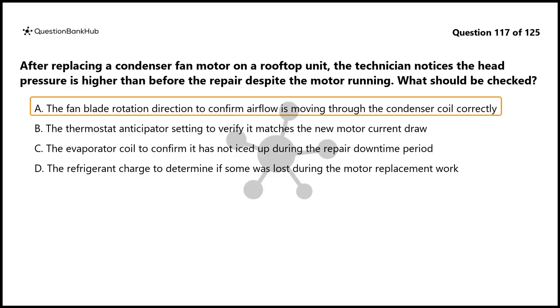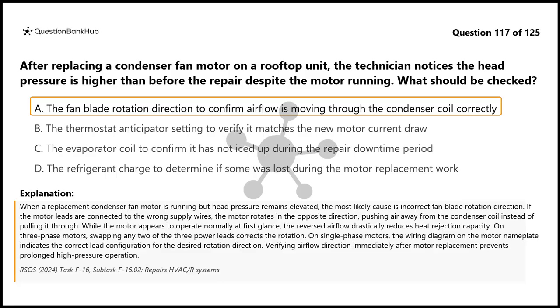The correct answer is A. When a replacement condenser fan motor is running but head pressure remains elevated, the most likely cause is incorrect fan blade rotation direction. If the motor leads are connected to the wrong supply wires, the motor rotates in the opposite direction, pushing air away from the condenser coil instead of pulling it through. While the motor appears to operate normally at first glance, the reversed airflow drastically reduces heat rejection capacity. On three-phase motors, swapping any two of the three power leads corrects the rotation. On single-phase motors, the wiring diagram on the motor nameplate indicates the correct lead configuration for the desired rotation direction. Verifying airflow direction immediately after motor replacement prevents prolonged high-pressure operation.